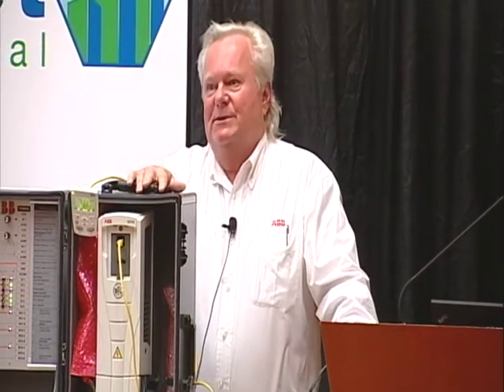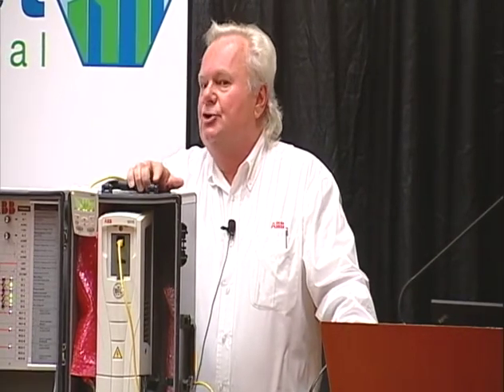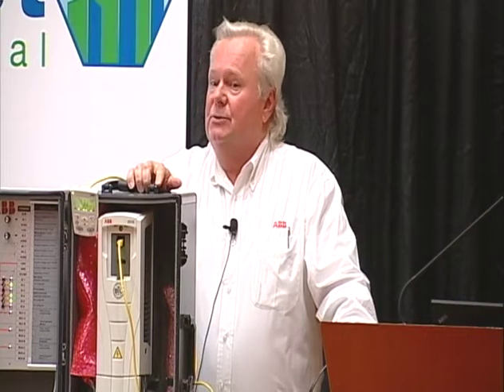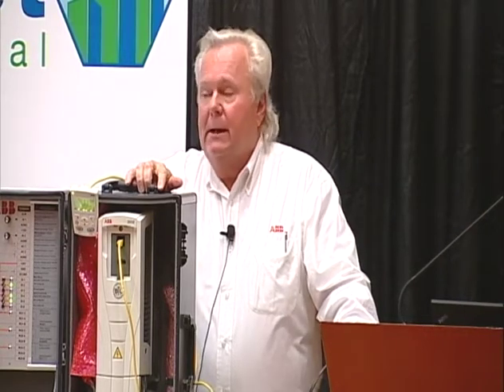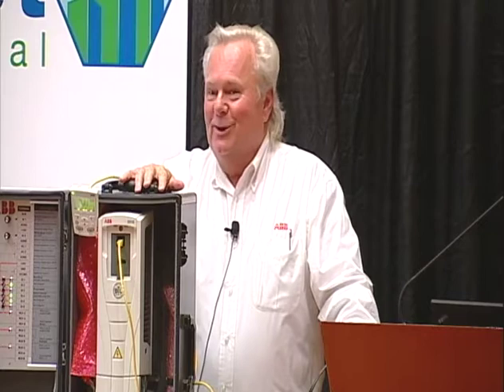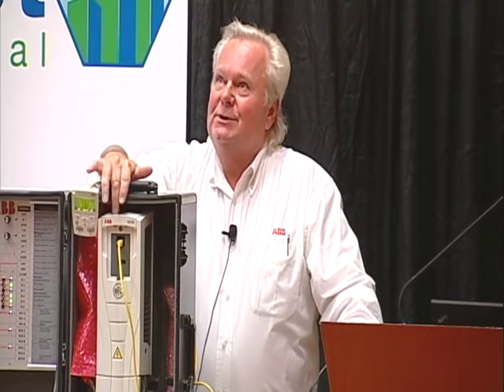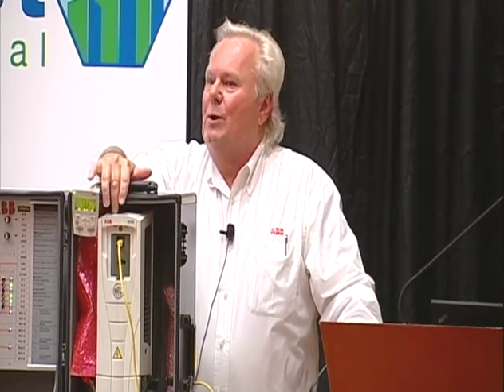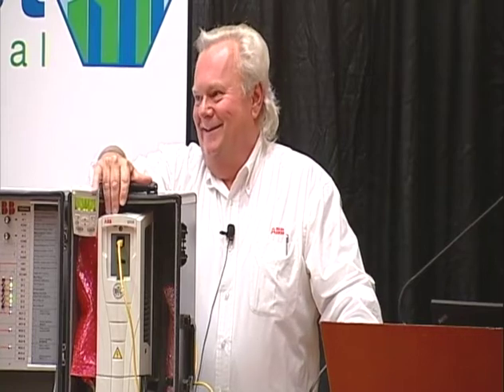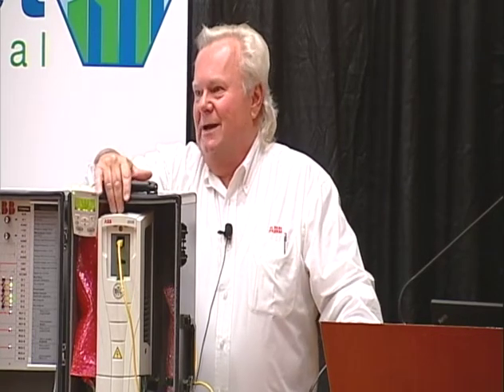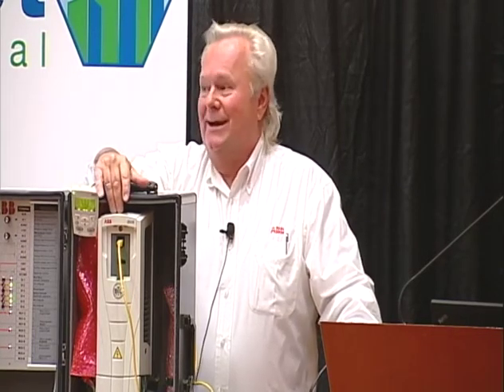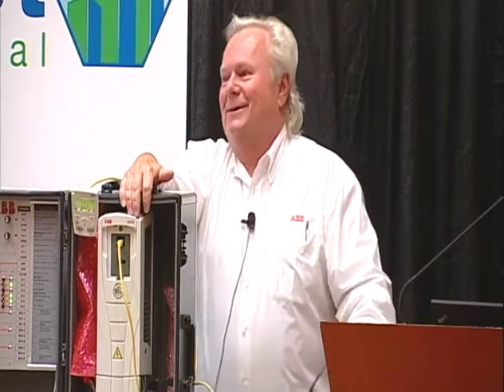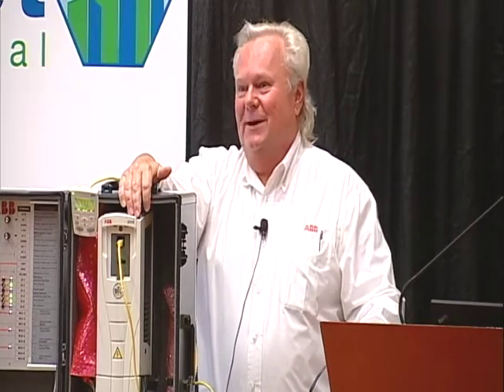With our bypass, which consultants specify on about 70% of what we ship every month, has a drive and a bypass. I don't agree with that because drives are very reliable. The failure rate on this product in the first 2 years is 0.17%. So two drives out of 1,000 fail in the first 2 years, 998 don't. So to me, a bypass is a waste of money, but consultants are specifying it 70% of the time, 70% of what we ship has a bypass, okay?